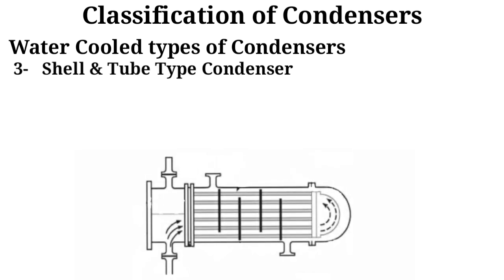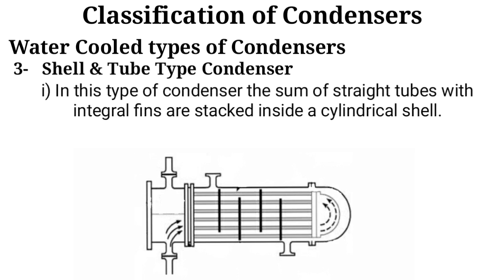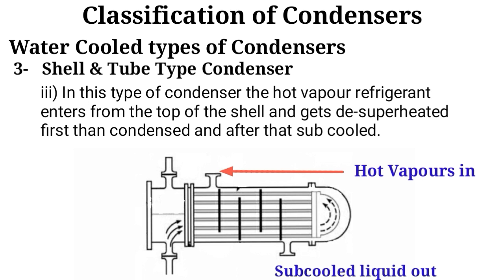In the shell and tube type condenser, a number of straight tubes with integral fins are stacked inside a cylindrical shell. These types of condensers are very popular in the refrigeration industry. The hot vapor refrigerant enters from the top of the shell and gets desuperheated first, then condensed and converted from vapor form to liquid form, and finally the liquid refrigerant is subcooled. It transfers the refrigerant heat to the water, warming the water at the outlet of the condenser shell.